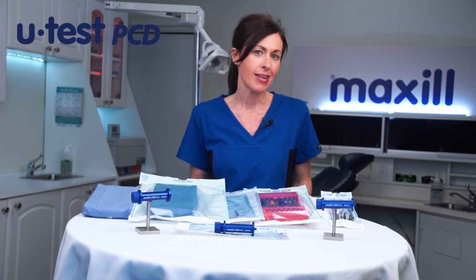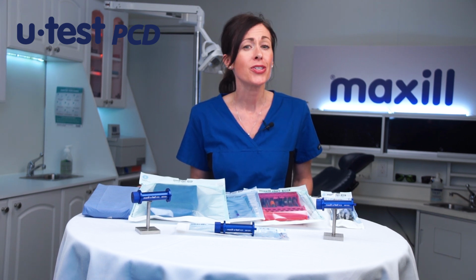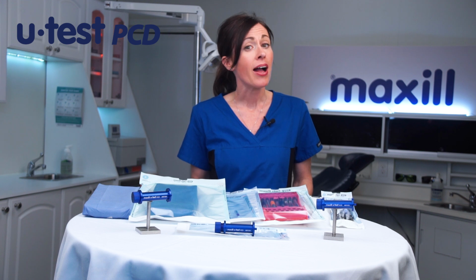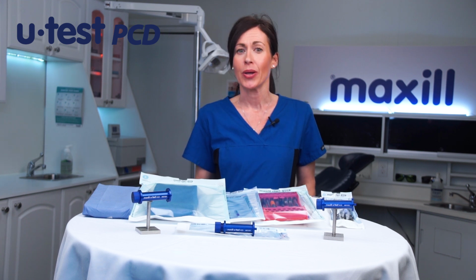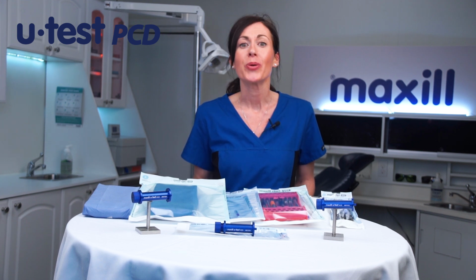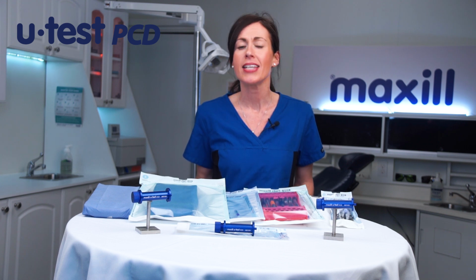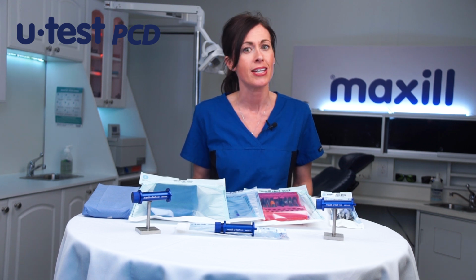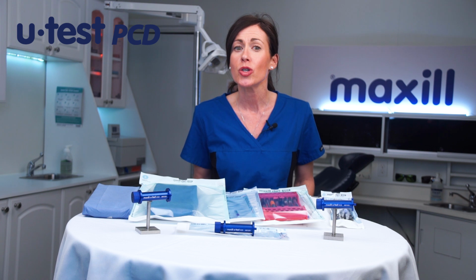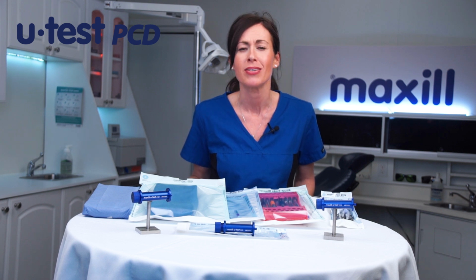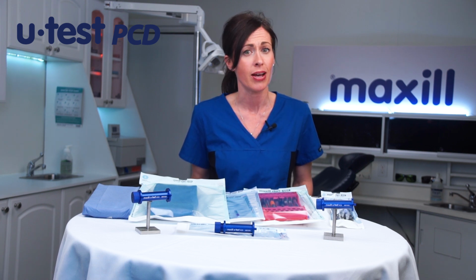The CDHO states that we must test for the efficacy of our sterilizers daily: a BI every morning, and a CI in every load. A PCD, a process challenge device, is a test device intended to provide a challenge to the sterilization process that is equal to or greater than the challenge posed by the most difficult item routinely processed.